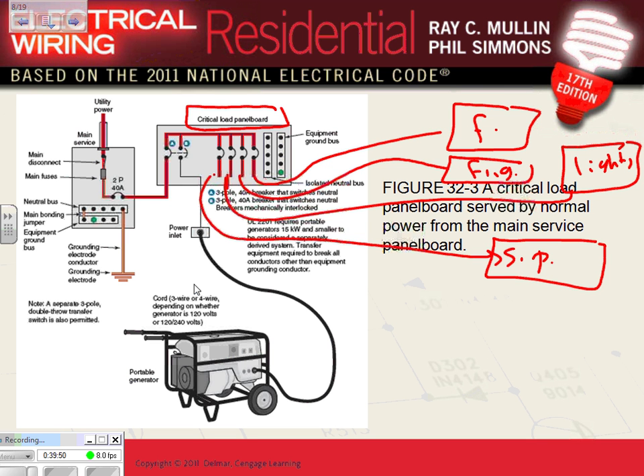So look how this system works. You go to your house, here's your service. Inside your service, guys, you have your panels. And I'm not going to tell you what you have here. Nick, you have the grounding, the neutral bus, and the main ground bus here. You bond them together. Can you guys see the bonding here? This is typical. Can you see the bond between the neutral and the ground? And then you pull a grounding electrode conductor, and we all know how to do that. That's inside your service. Up to this point, every one of us has this panel in our homes, right?